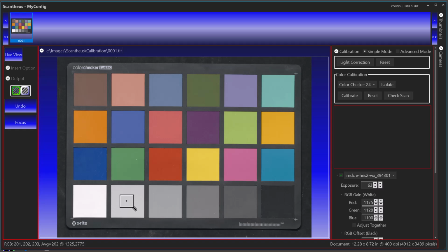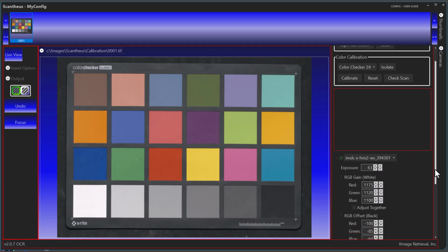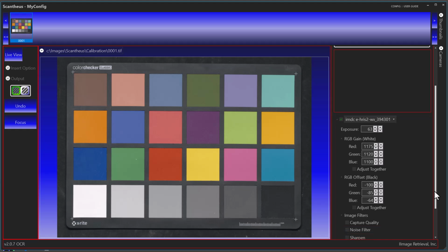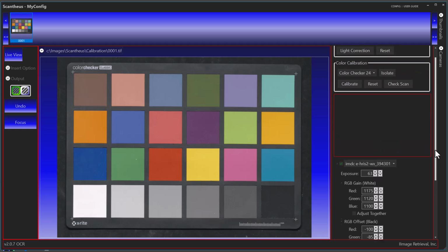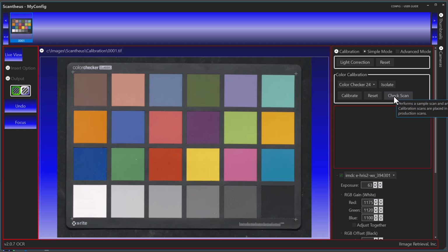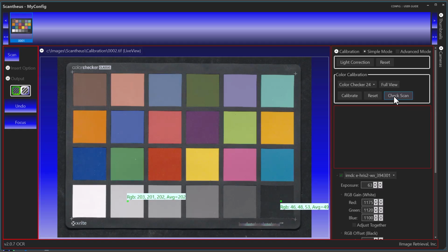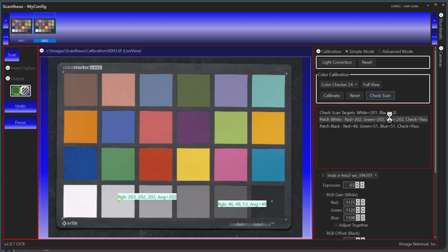Our target for that patch is 201. Now, if we're within 3 of the target value, so 3 less or 3 more, we're calibrated. Here's the settings. It changed. You notice, if you remember, our gain was 1,000, and it bumped them up to get calibrated. Now, a better way to check your scan is this check scan. And what that does is it does a scan, and then it analyzes those two patches and tells you pass or fail. So because they're within 3, the white's a little high there by 1, but it's still within the margin of error of 3.